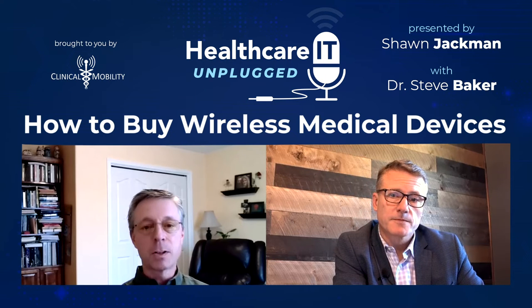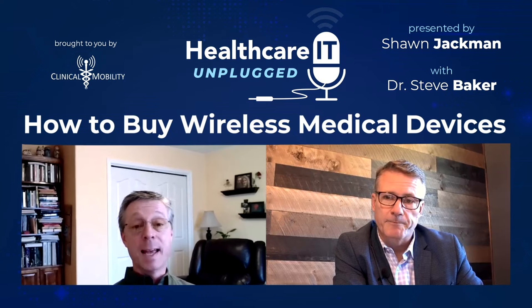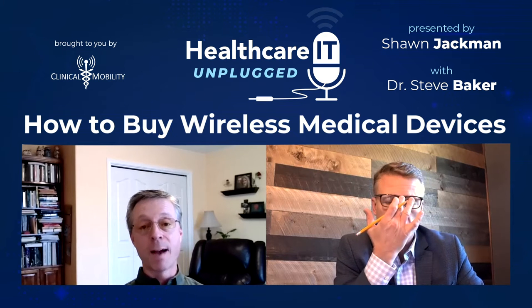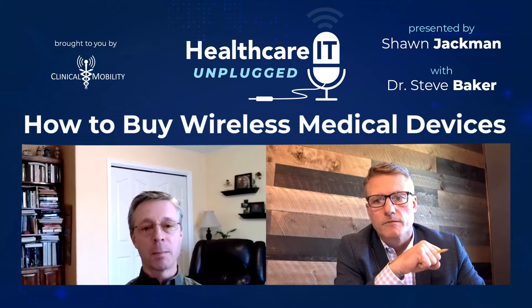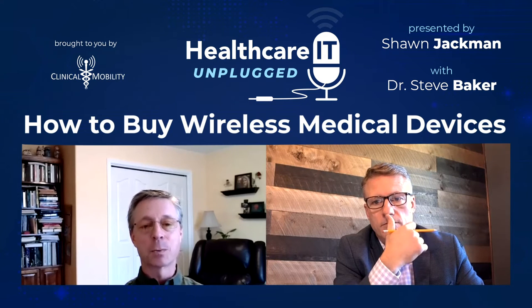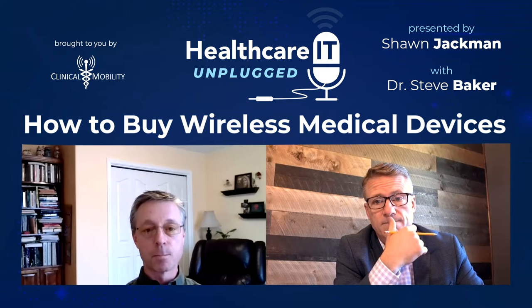Well, if you're delayed by 1 second to get a no heartbeat alarm, that's okay. 6 seconds and higher is pushing it. 10 seconds is our requirement. We have to, from the onset of an alarm condition, enunciate the alarm within 10 seconds. So if we've used 6 seconds, that's really pushing against the limit.